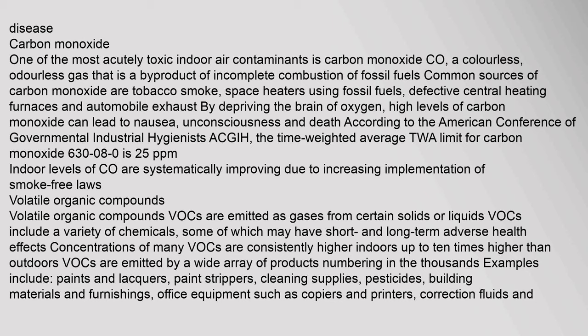One of the most acutely toxic indoor air contaminants is carbon monoxide (CO), a colorless, odorless gas that is a byproduct of incomplete combustion of fossil fuels. Common sources of carbon monoxide are tobacco smoke, space heaters using fossil fuels, defective central heating furnaces, and automobile exhaust. By depriving the brain of oxygen, high levels of carbon monoxide can lead to nausea, unconsciousness, and death. According to the ACGIH, the time-weighted average (TWA) limit for carbon monoxide is 25 ppm.